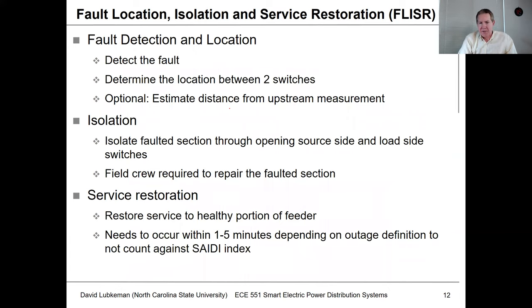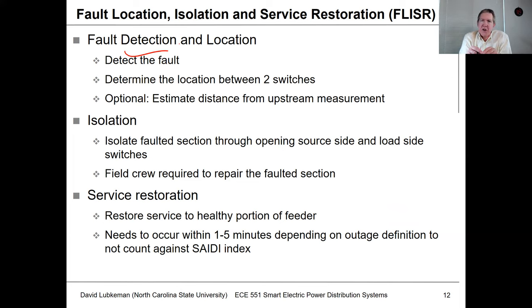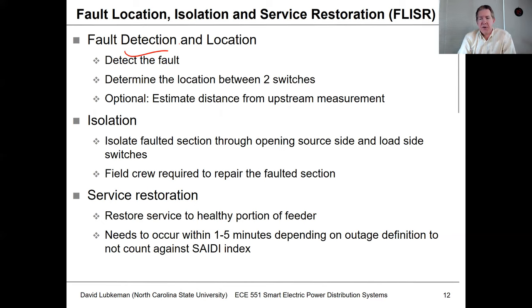For the FLISR process — different utilities use different terminology, but FLISR clearly tells you what this is. The FL in FLISR stands for fault location, though you have to detect the fault first, so I talk about fault detection and location. Then you have isolation — disconnecting the fault on the high side and possibly the load side, switching open both upstream and downstream locations. Once you've isolated the fault, you can do the service restoration.